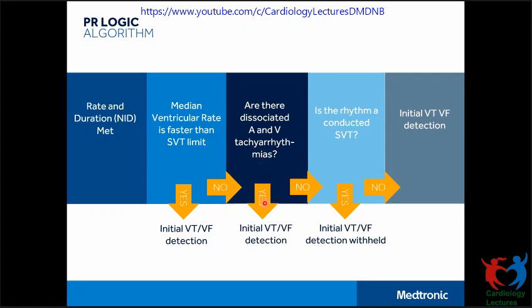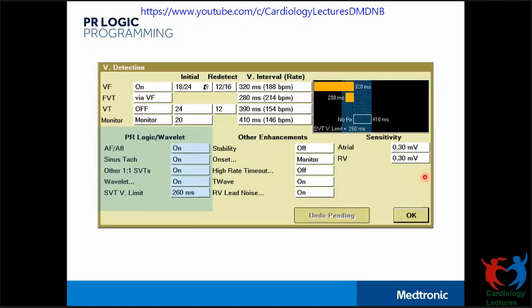If the ventricular rate is faster than the SVT limit, it proceeds with initial VT detection. If not, it looks for AV dissociation. If the A and V are dissociated, it proceeds with detection. If not, it looks for whether the rhythm is SVT — if yes, it withholds detection; if no, it proceeds with detection. On the programmer screen, PR Logic is found above Wavelet, with three distinct programmable features: one for atrial fibrillation and atrial flutter, one for sinus tachycardia, and one for other 1:1 SVTs.